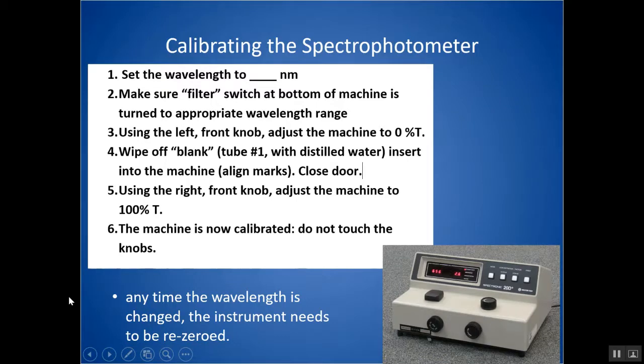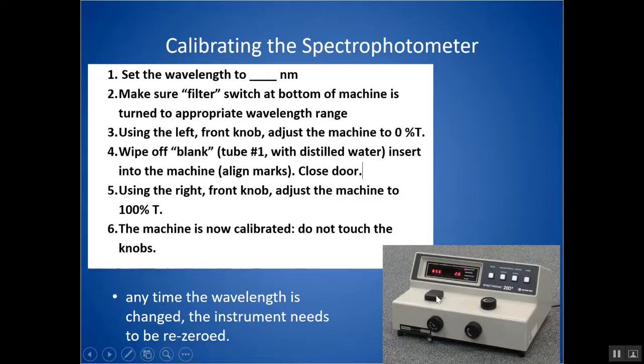Steps to calibrate the spectrophotometer to your blank: first, set the wavelength to whatever you need for the experiment. Sometimes there's a filter switch at the bottom to set to the appropriate wavelength range. Without anything in the machine, turn the left knob and adjust to 0% transmittance — teaching it that when nothing's in it, no light is passing through. Then prepare your blank, fill a cuvette with distilled water, put it in the machine with the door closed, and adjust to 100% transmittance — teaching it that the blank represents 100% transmittance. Now you have calibrated the machine.